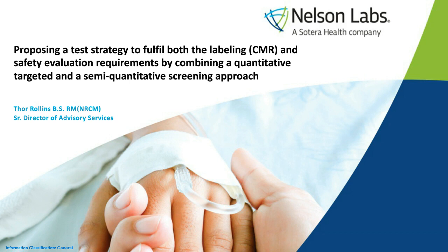And for those of you that maybe are not familiar, hopefully most of you are, the CMR stands for carcinogens, mutagens, and reproductive toxins. And this is mostly coming from the Annex 1, Section 10.4 of the new MDR, the medical device regulations that are coming effective in May. That was pushed back a year because of COVID for Europe. So if you are working with a notified body to have a CE mark in Europe, I'm hoping you're familiar with the MDR and specifically this Section 10.4.